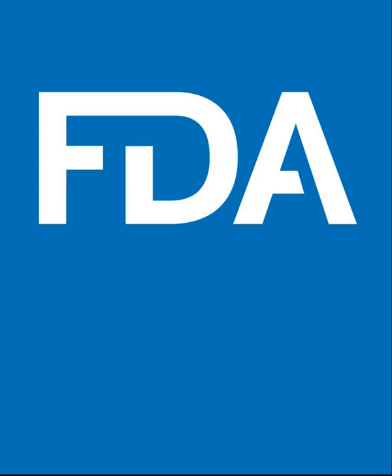It allows FDA to determine whether the device is equivalent to a device already placed into one of the three classification categories. Thus, new devices not in commercial distribution prior to May 28, 1976 that have not been classified can be properly identified. Any device that reaches market via a 510(k) notification must be substantially equivalent to a device on the market prior to May 28, 1976, a predicate device.